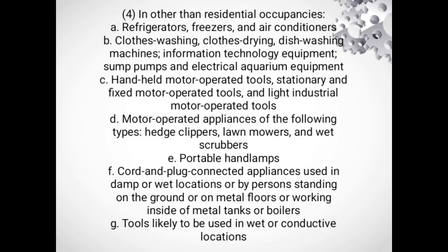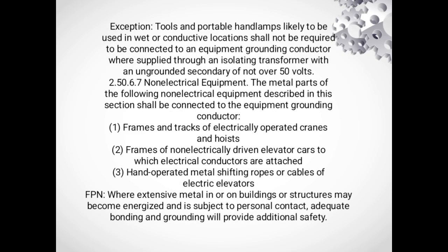This slide addresses when non-current carrying metal parts of equipment must be connected to a grounding conductor. The goal is to protect personnel from shock hazard. This includes equipment in wet location, near grounded objects, or running at high voltage. Exception: tools and portable lamps likely to be used in wet or conductive location shall not be required to be connected to an equipment grounding conductor where supplied through an isolating transformer with an ungrounded secondary of not over 50 volts.